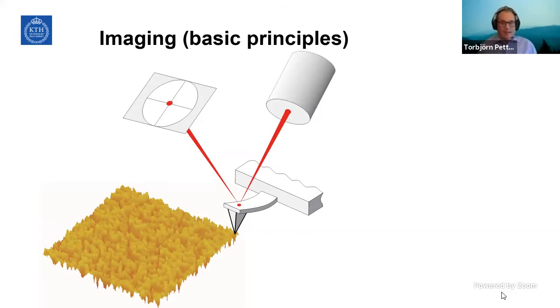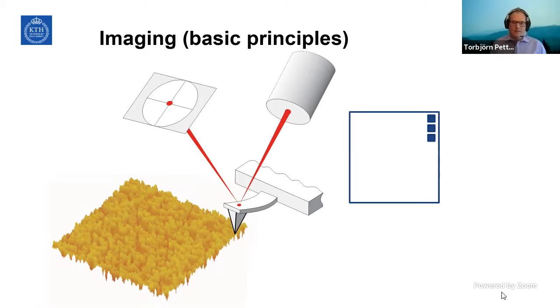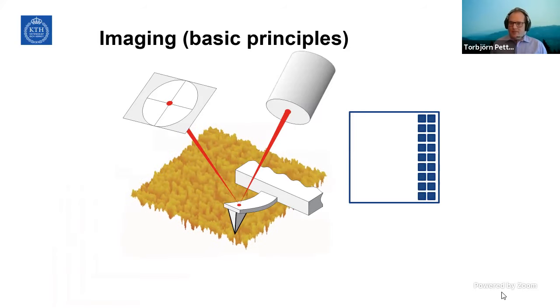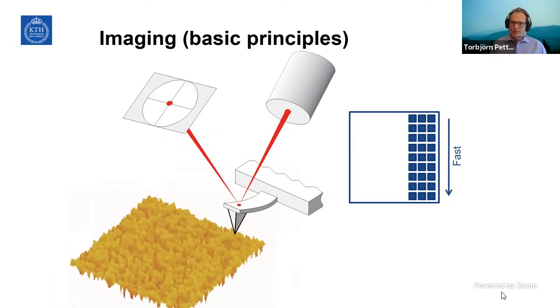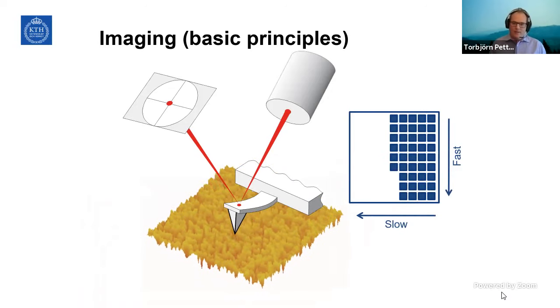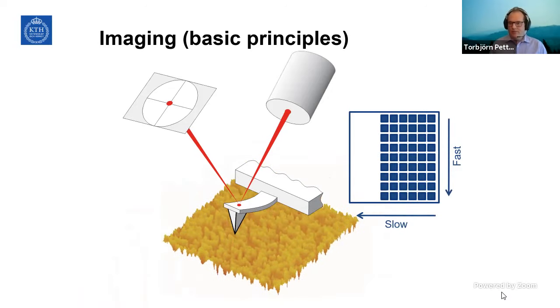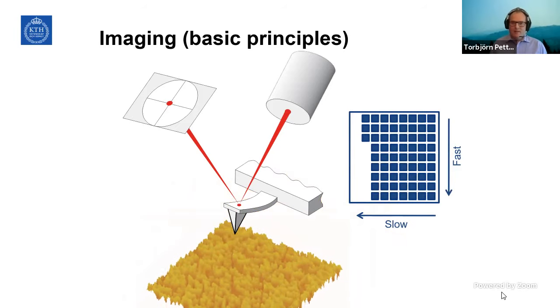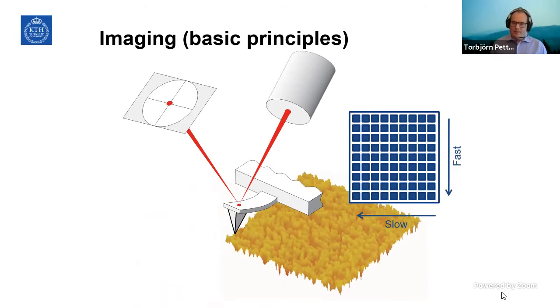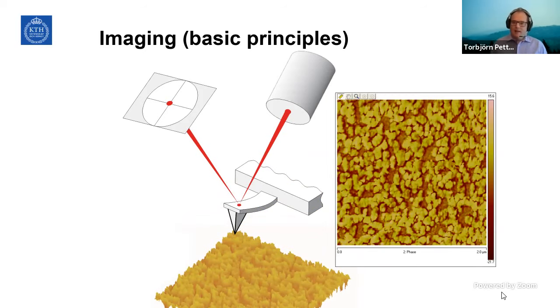To do this, we're using AFM, atomic force microscopy. Most of you probably know about AFM as an imaging tool. And in imaging, we use the AFM as a sharp tip, rastering over a surface, capturing data from different positions of the surface, building up a three-dimensional surface structure of the material so we can see the topography or some other type of interaction parameters during the imaging. And this three-dimensional structure is normally published as an image, or we can get a surface roughness parameter.